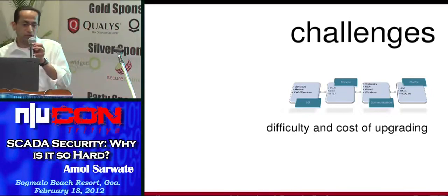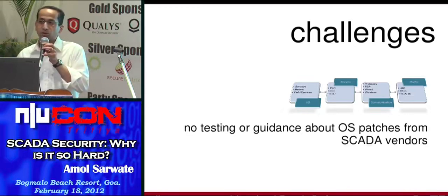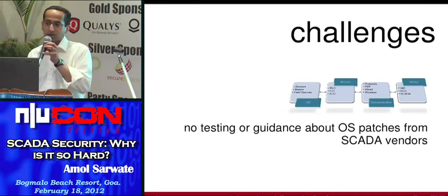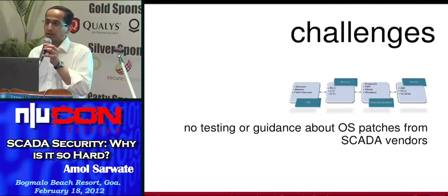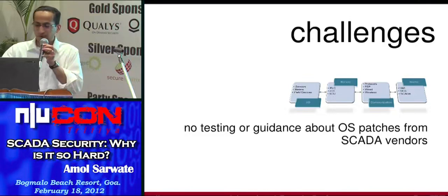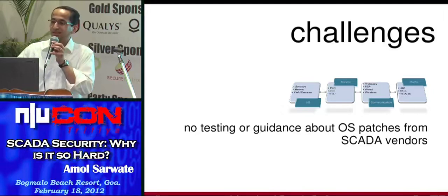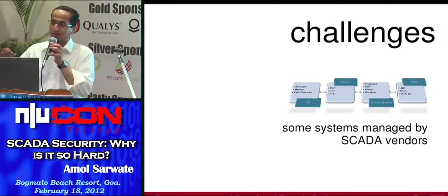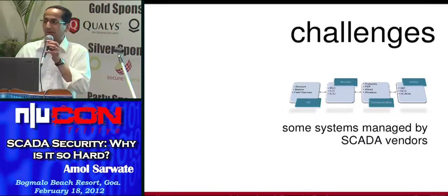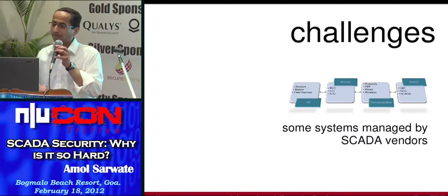There is no OS patch guidance from vendors. Some systems are managed directly by the vendors, so if a security consultant is called in to do penetration testing or at least to find the security posture, we go in and we see a Windows system. It's okay, we can easily find the security posture of a Windows system, but that system is not really managed by the owner, it's managed by the vendor, so they don't even have administrative privileges on it. They can use the HMI software, but don't have administrative privileges. So you cannot even see registry keys and do a simple auditing of a Windows system.